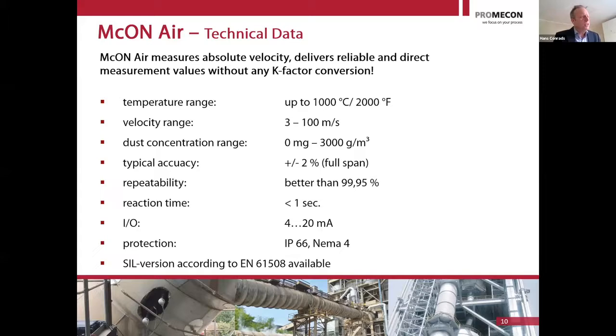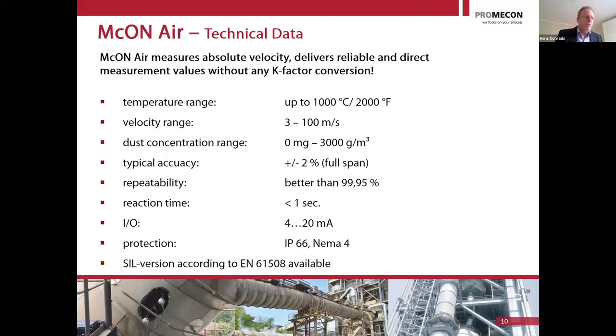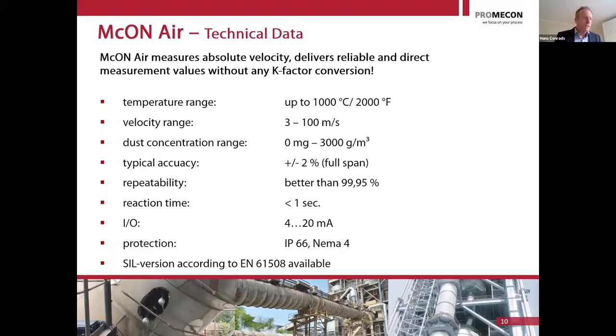We are talking about velocity measurements of gases ranging up to 1,000 degrees C, or 2,000°F. Velocity ranges are between 3 and 100 meters per second. Our system is a linear measurement — we do not have a squared relationship like delta pressure measurements. So we have a very wide and linear measurement span.